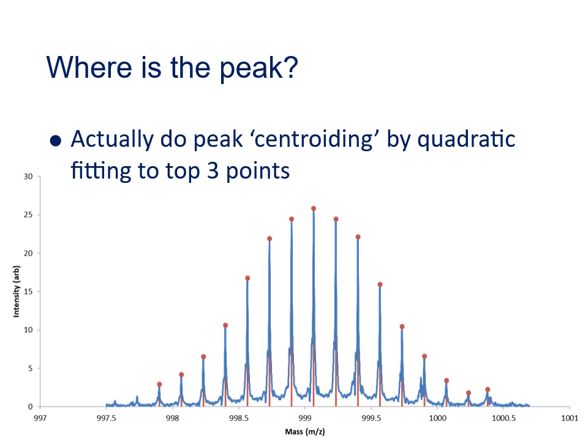So as a quick recap, in a profile mode mass spectrum you can see the noise and the complete shape of all the peaks in the spectrum. Whereas in the centroided spectrum you can just see the peaks as sticks, with no noise in between them. And in order to generate the centroided spectrum, at some point a peak threshold must have been set, and any peaks below that will be missing from the centroided spectrum.